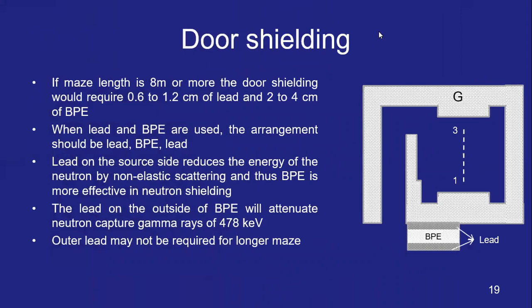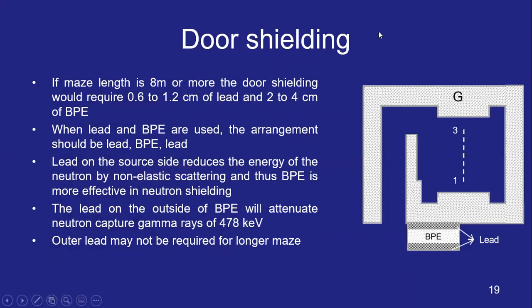If the maze length is 8 meters or more, door shielding requires 0.6 to 1.2 centimeters of lead and 2 to 4 centimeters of BPE. When lead and BPE are used, the arrangement must be: lead, then BPE, then lead. The lead on the source side reduces neutron energy by inelastic scattering, making the BPE more effective for neutron shielding by thermalizing them. The outer lead attenuates neutron capture gamma rays of about 478 keV. The outer lead may not be required if the maze is very long.